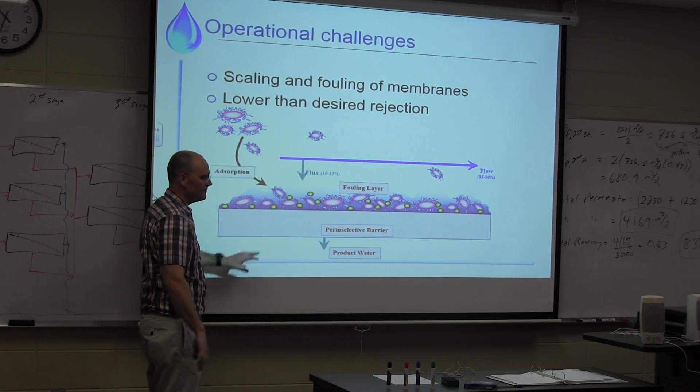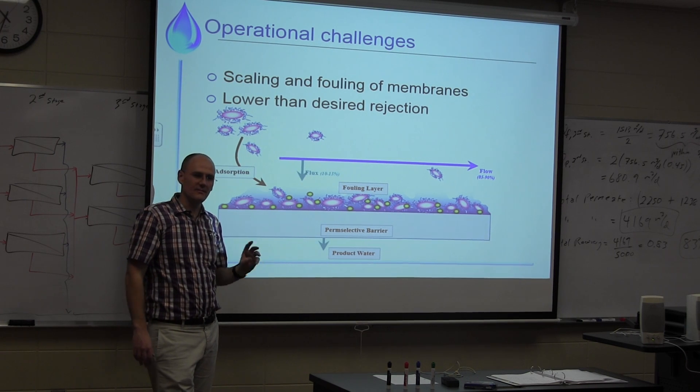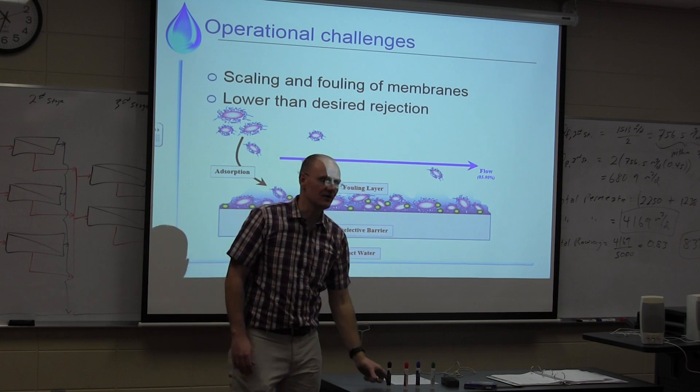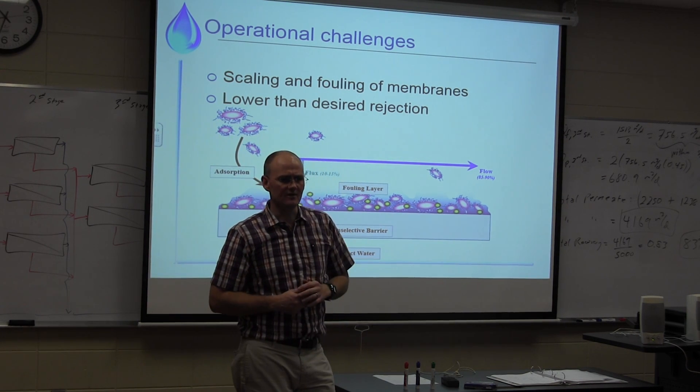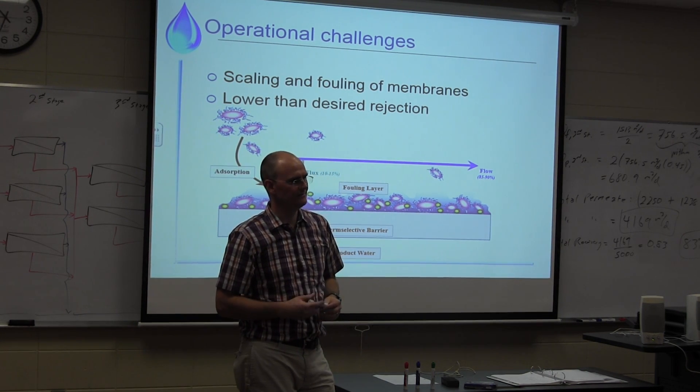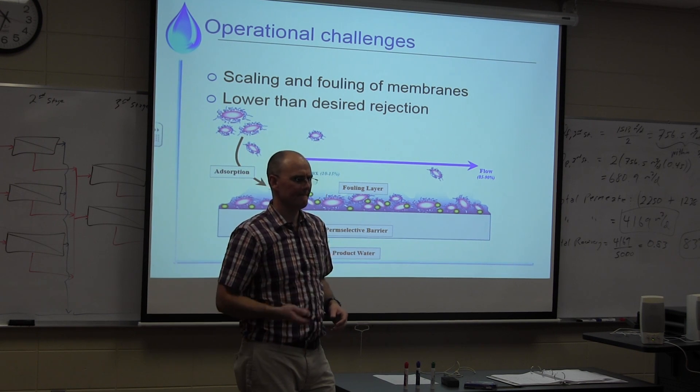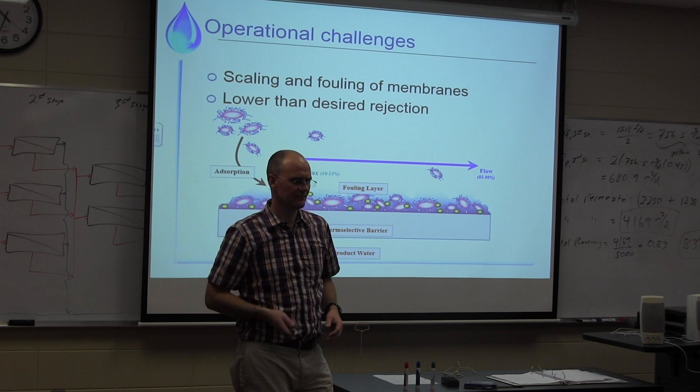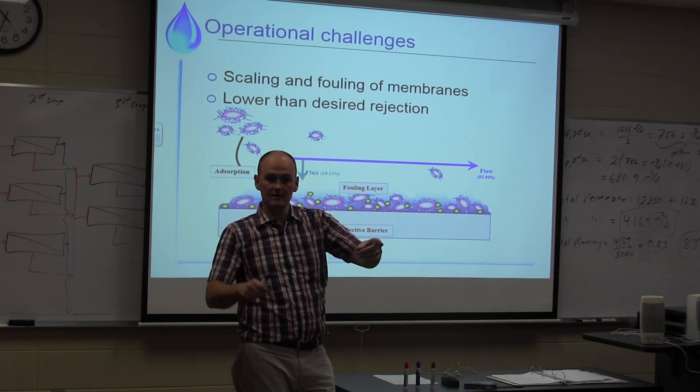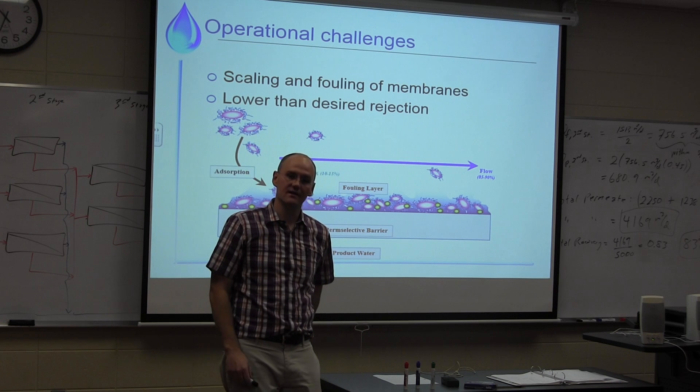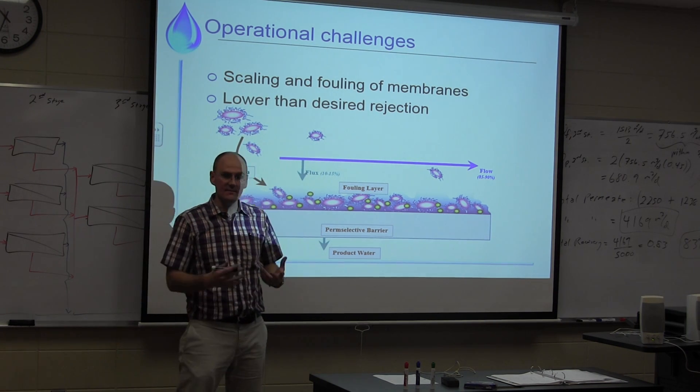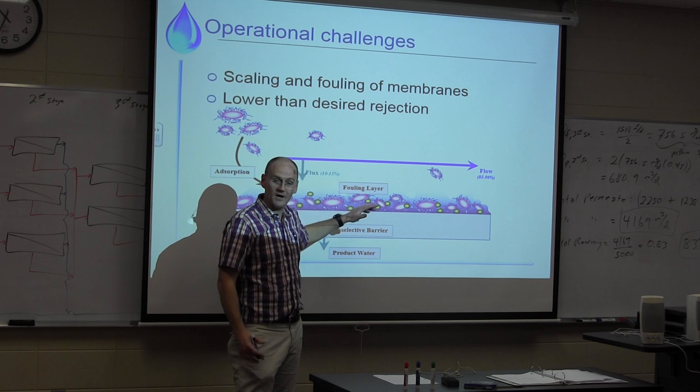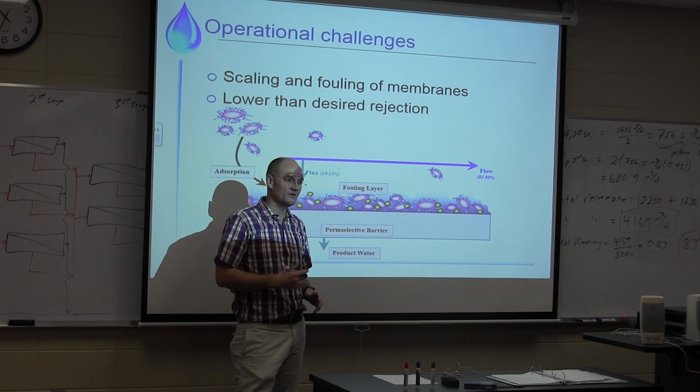You don't get this biofilm formation in microfiltration and ultrafiltration. Why do you think that is? Knowing what you know about MF and UF now, why don't you get a biofilm forming? How did we operate MF, UF? Dead end. The backwash. That's right. In MF and UF, we backwash it really regularly. And that kind of prevents a biofilm from forming because it's continually being backwashed.